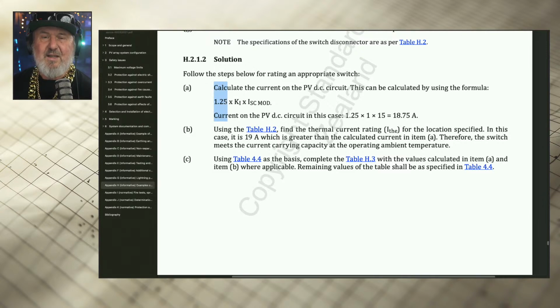So this 1.25 times is additional to allow for a bunch of things. So modules have a certain amount of variation in their manufacture. So you'll see that their ratings will typically be 0 to plus 5%. So you might end up with all your modules being 5% higher rated. So that's going to mean that you have more current. But the big one is irradiance. Now, panels are tested, and that's what the ISC module is, at 1,000 watts per square metre. In Australia and New Zealand, because we're in the southern hemisphere, and woohoo if you live in Africa as well, you've got very clear skies. And certainly when the clouds aren't there, there's not a lot of particulates that reduce the irradiance. So we get more than 1,000 watts per square metre on a clear day, particularly in spring, I find. I've seen 1,200 watts per square metre.